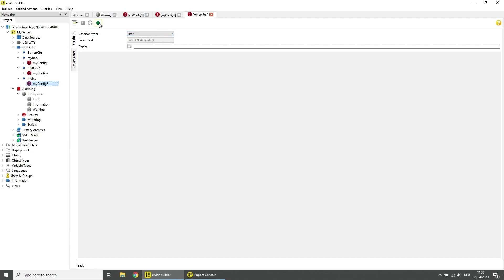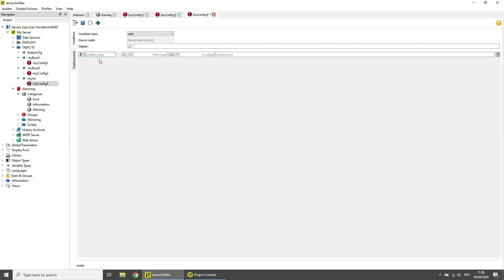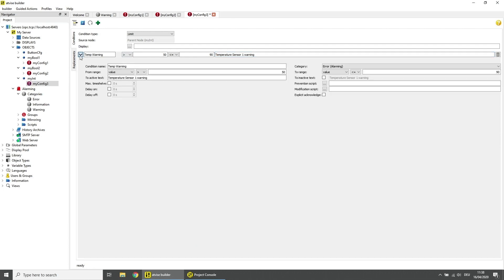Click on the plus icon to add an alarm condition and enter a name for the condition. Now choose the comparison operation and the range so that for a value between 50 and 90 an alarm will be triggered. Open the extended settings and choose Warning as the alarm category.